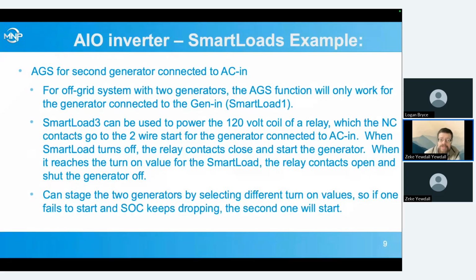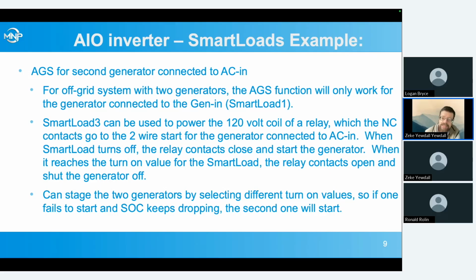Another thing you can do with a smart load is simulate an AGS for a second generator. If we've got a big off-grid system, we might have two generators, one of them going into the generator input and one going into the AC in, where we would normally have the grid connected. The AGS function only works with the generator connected to the gen in, the smart load 1. So what we can do is take one of our other smart loads and use it to power the coil on a relay, and then we've got a normally closed contact on that relay that controls the 2-wire start for the generator.